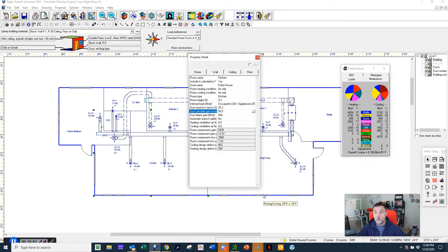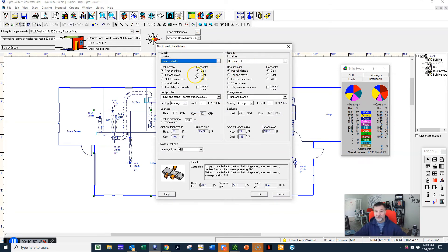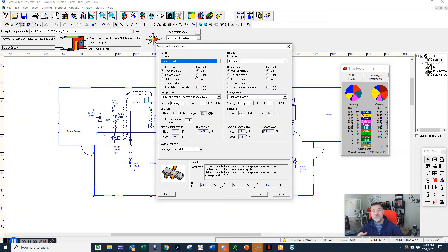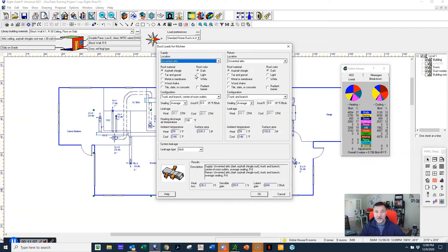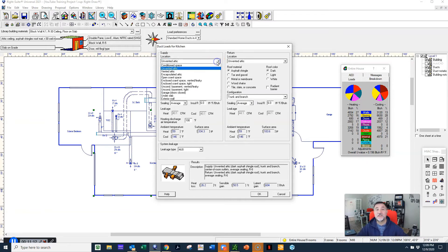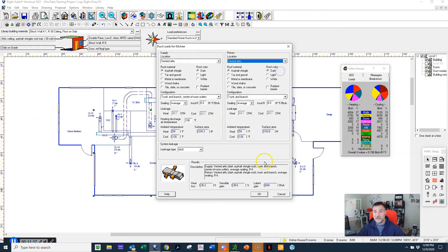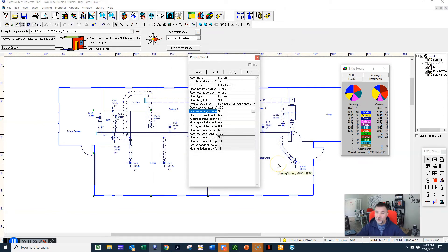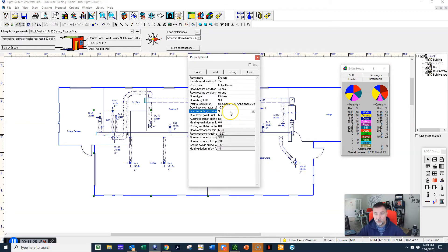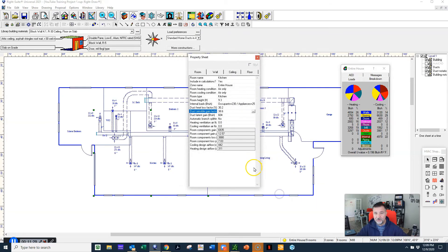It almost doubles. So that means the heat—if we had this set incorrectly because we were trying to manipulate the system—we're going to cause the system to think that it has more heat coming into the building that it needs to get rid of, which is going to cause someone to oversize the system. Now let's put this in a vented attic instead of unvented and let's see what this does. It dropped it a little bit because with the ventilation it helps to reduce the humidity and the temperature in the room. So it's very important—there's so many different factors involved in doing a Manual J calculation properly.